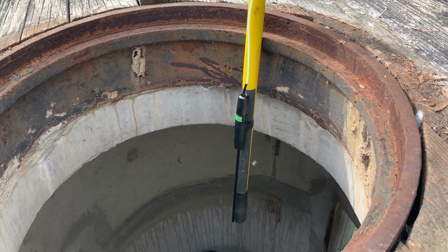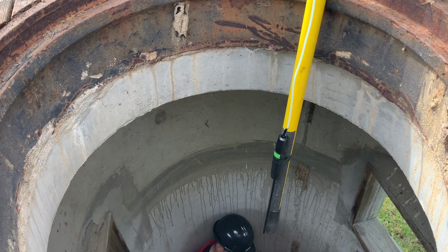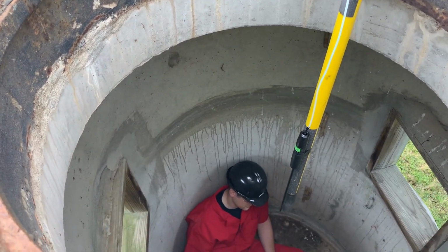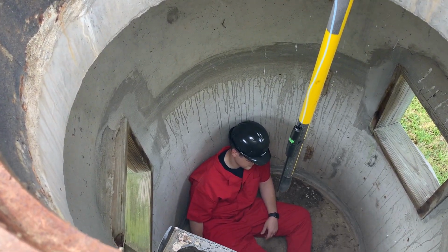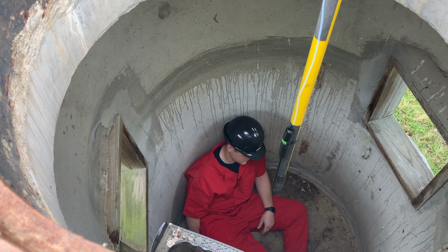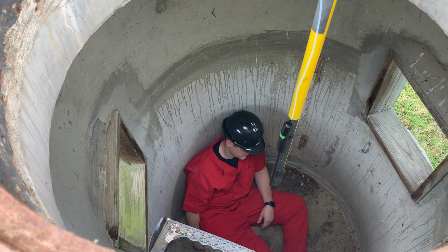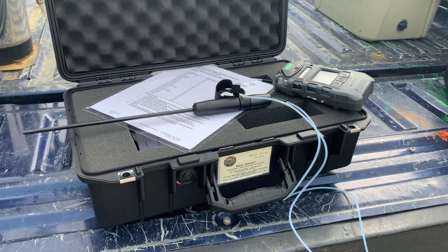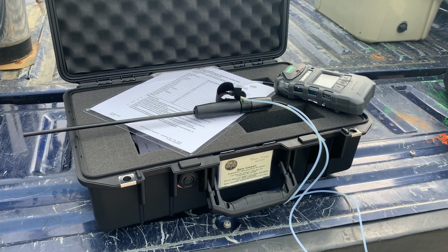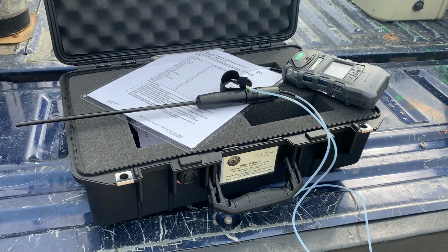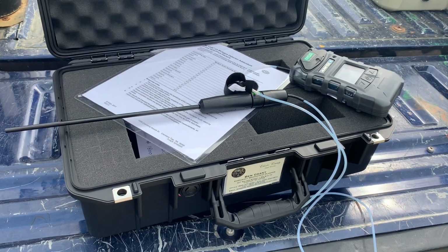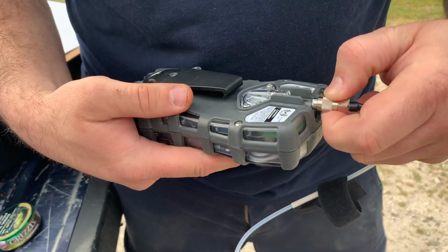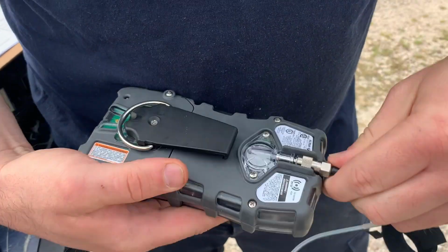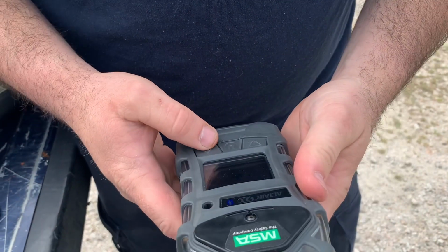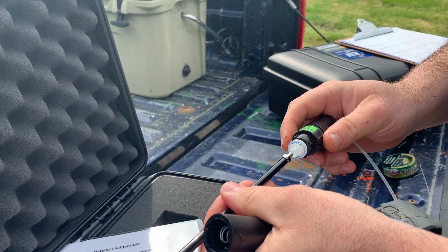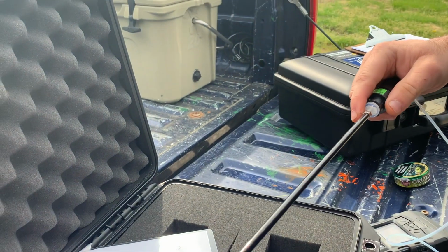The confined space scenario will demonstrate the proper procedure for using the Multigas Detector to determine entry precautions for confined space entry. The method will also demonstrate vertical air sampling using an air sampling probe and a 10-foot line. The probe and line accessory allows for vertical drop air sampling up to 11 feet. Attach the probe to the pump inlet located on the back of the gas detector. Then connect the probe to the line accessory.